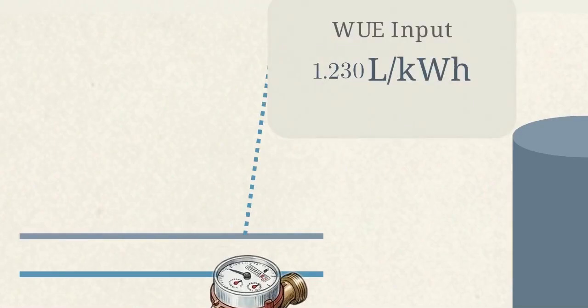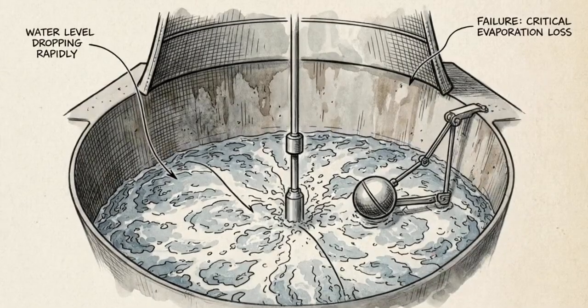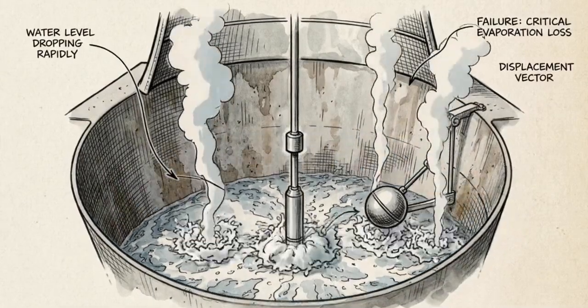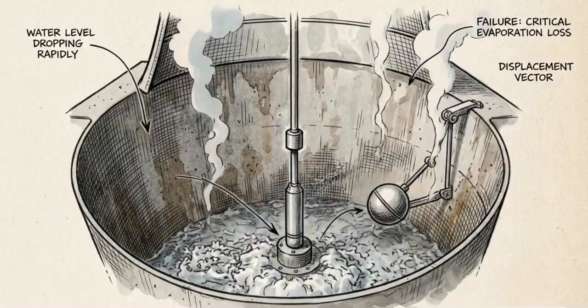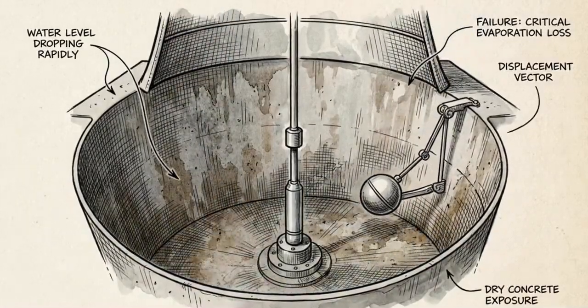By attaching digital interfaces to the facility's existing makeup water meters, operators extract live consumption data. This feeds directly into the Water Usage Effectiveness, or WUE metric, keeping the site compliant with strict sustainability targets. If an automated makeup valve fails, a cooling tower basin can quietly lose its water inventory. Evaporation continues, but the supply is gone.